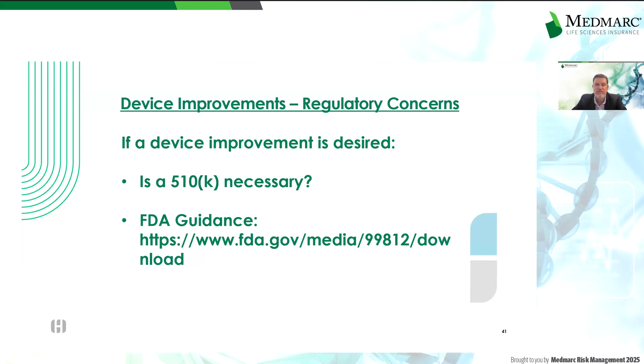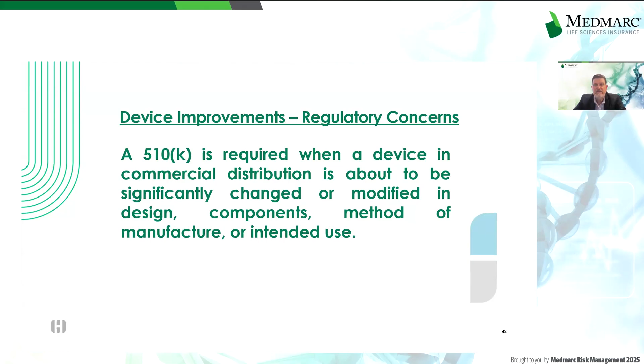FDA has published a guidance, which in essence is exactly that, when to file a 510K for your device improvement. The guidance provides as follows. A 510K is required when a device in commercial distribution is about to be significantly changed or modified in design, components, method of manufacture, or intended use. Of course, that begs the question, what is a significant change or modification. The guidance defines those as well. A change or modification in the device that could significantly affect the safety or effectiveness of the device, e.g., a significant change or modification in design, material, chemical composition, energy source, or manufacturing process, and/or a major change or modification in the intended use of the device.